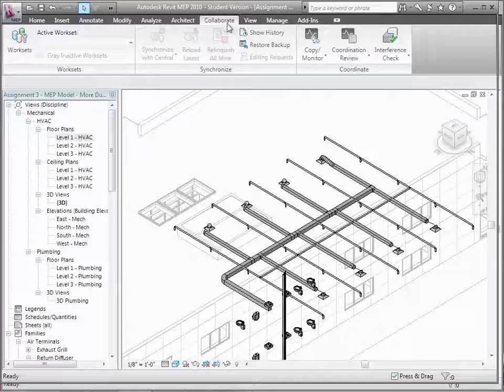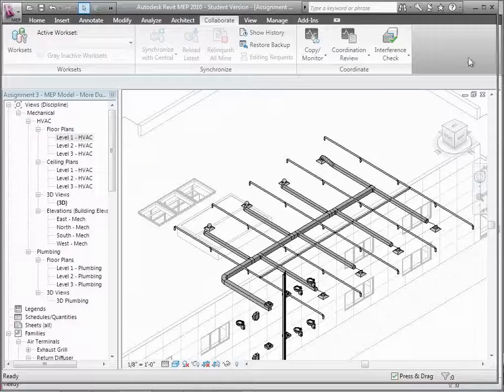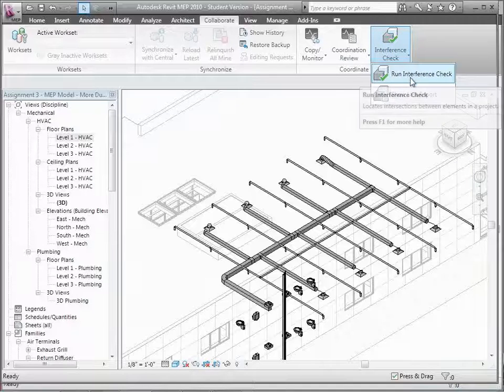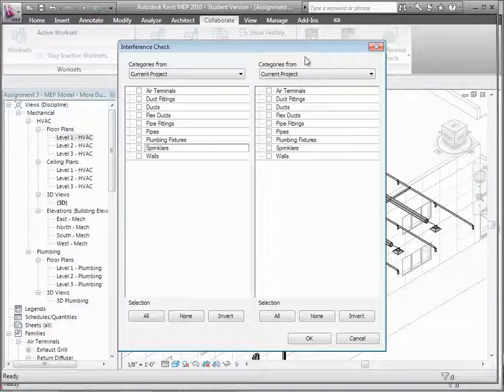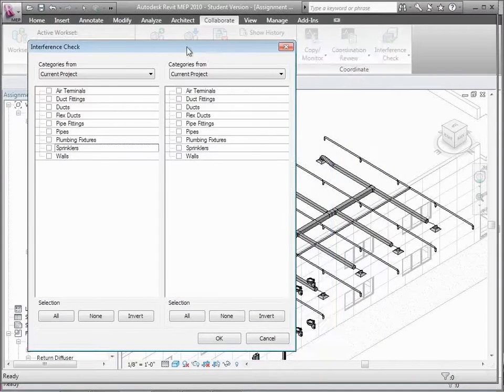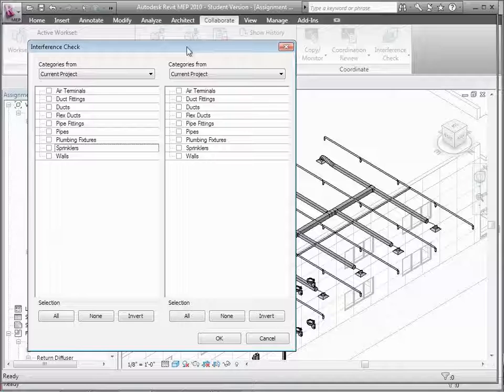Interference Checking is just looking for spatial interferences. There are no smarts behind it in terms of whether the system is working or whether you've done a good job designing it — it's really just spatially asking, are you overlapping me? If you run interference checking, you can choose categories of things you want to try intersecting. These categories are the same ones that show up in Visibility Graphics. Everything has a category: ducts, air terminals, sprinklers, walls.